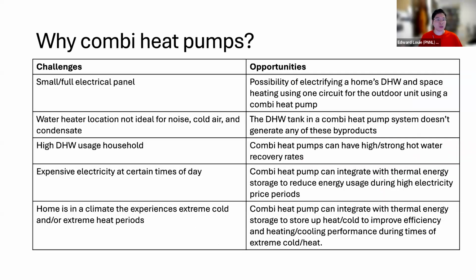Next slide. So why combis? Some of the problem-solving capabilities of combi make it a really good value, a product that could solve a lot of problems. One is that a lot of homes have small or completely full electrical panels. If you have systems where you need to add multiple new circuits, it could be very expensive to upgrade the panel or the service entrance. Combi systems have the possibility of doing domestic hot water electrification and space heating electrification all in one circuit. If the home has a central air conditioning system, those are typically 30 amp 240-volt circuits. Combi systems could take over from the air conditioning and reuse that same circuit, and then you can take care of domestic hot water, space heating, and space cooling all in that one circuit. That would save a lot of money on the electrical upgrade side.